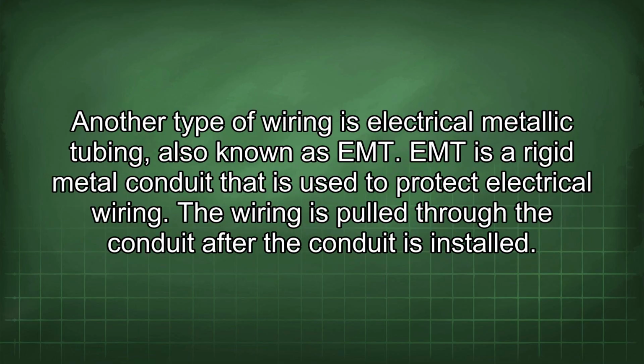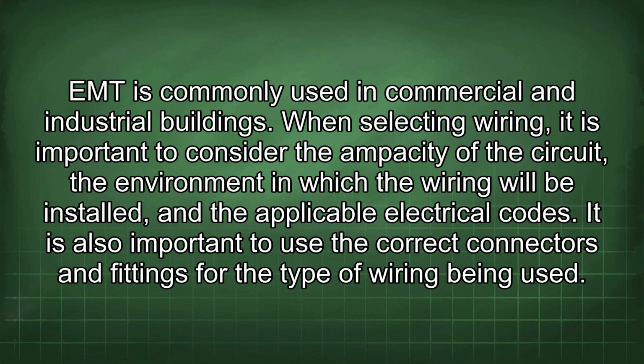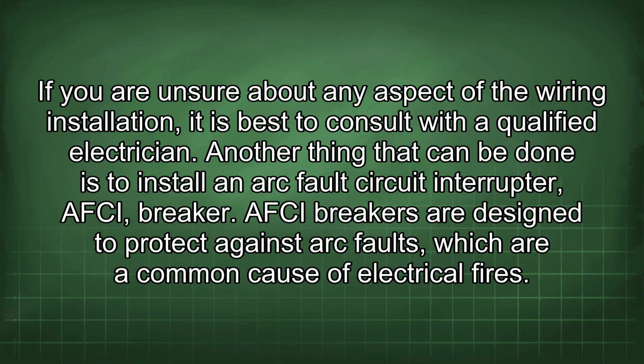Another type of wiring is electrical metallic tubing, also known as EMT. EMT is a rigid metal conduit that is used to protect electrical wiring. The wiring is pulled through the conduit after the conduit is installed. EMT is commonly used in commercial and industrial buildings. When selecting wiring, it is important to consider the ampacity of the circuit, the environment in which the wiring will be installed, and the applicable electrical codes. It is also important to use the correct connectors and fittings for the type of wiring being used. If you are unsure about any aspect of the wiring installation, it is best to consult with a qualified electrician.